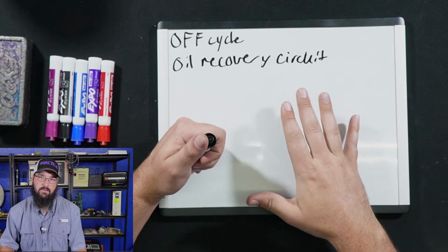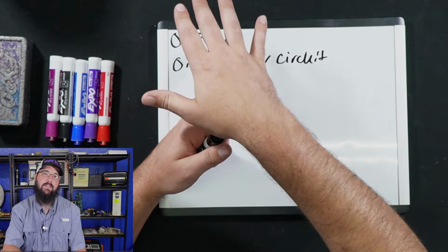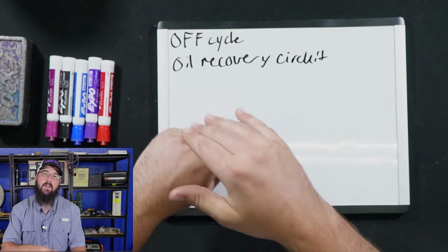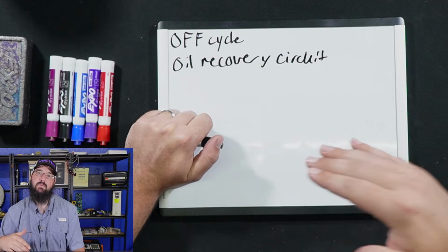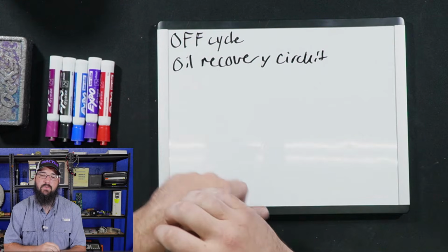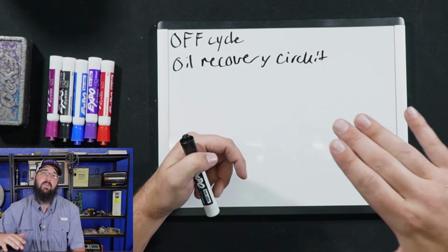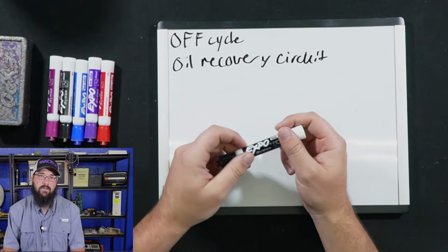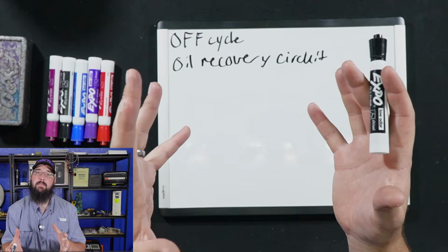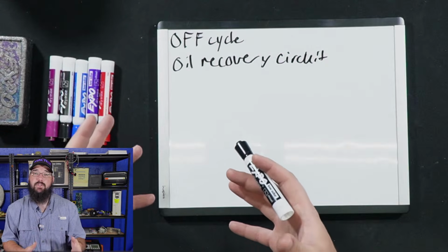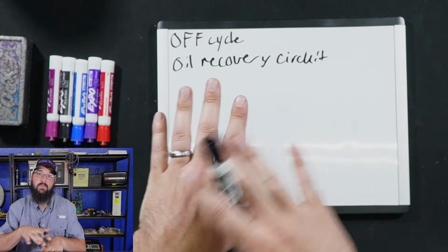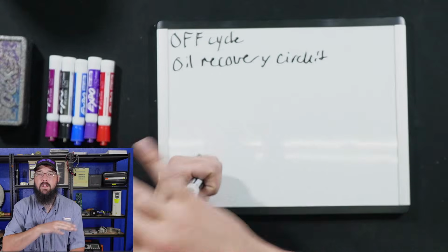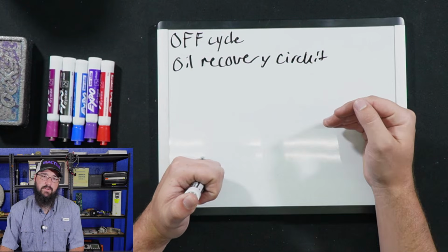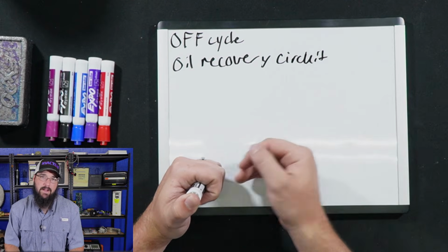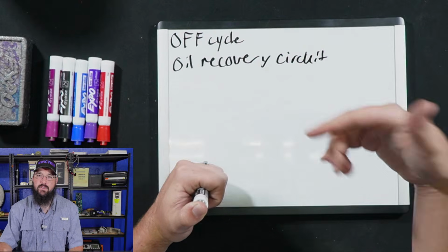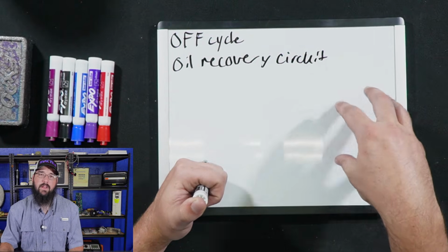So if the evaporator level starts to run too low, then the eductor can't access the oil, which is sitting on top of the refrigerant. And if the liquid level begins to run too high, then all that's going to be coming back into the eductor is straight liquid refrigerant, because our oil gets pushed up above where the eductor is pulling off of. So that's part of what we're having to balance, but that's going to lead to a migration eventually. If we can't stay within our designed liquid level point on that heat exchanger, then our eductor system cannot access that oil and get it back out of the evaporator into the oil sump. So eventually, you let that run long enough, that's going to cause a migration issue.